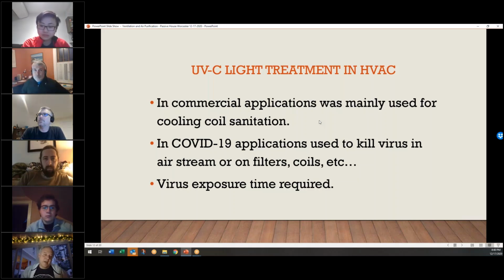I mean, obviously in hospitals and applications like that, it was used, but for general commercial HVAC, if you had a UV light, it was probably stuck right up against the cooling coil, and its purpose was to keep that coil clean. The thing with UVC light is, the virus has to be exposed to it for a certain amount of time. So if you have just one UV light at the filter rack, maybe the air is moving about 500 feet per minute, so it doesn't spend a lot of time in that light. So you realistically either need to slow that air way down, or you need to put multiple UV light bars, for maybe 50 feet in your return air duct, to try and clean that air.